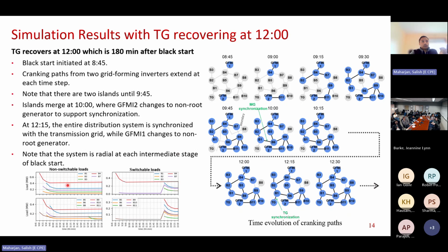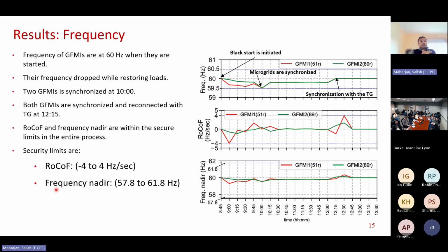And this diagram shows you the amount of switchable loads that are picked up at various instances and at various bus blocks. So it shows how much non-switchable load is picked up and how much switchable load is picked up. So you can see that switchable loads are picked up at the very end of the study period, mostly after the transmission grid comes online. So most of the switchable loads are picked up once the transmission grid is online. This is because of the finite energy capacity of the BES grid forming inverters. And non-switchable loads, since they are hardwired, have to be picked up as soon as the bus blocks are picked up.